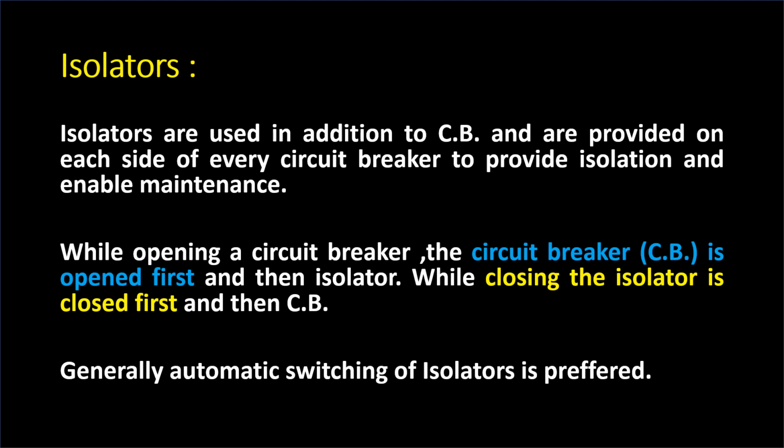Isolators are used in addition to circuit breaker and are provided on each side of every circuit breaker to provide isolation and enable maintenance. So isolation during maintenance is the main role of isolator.